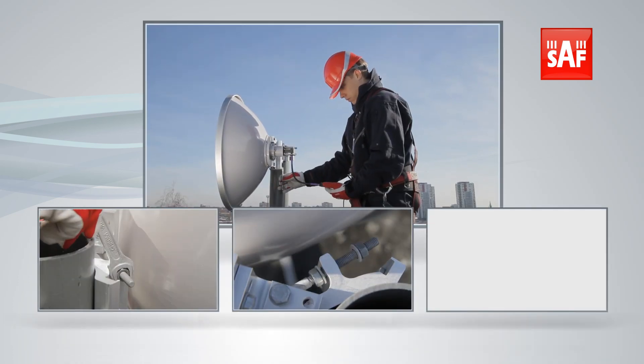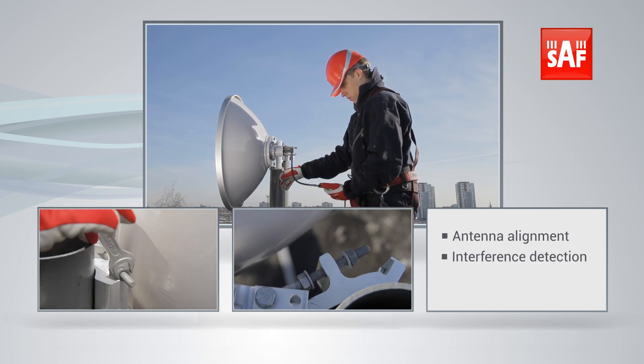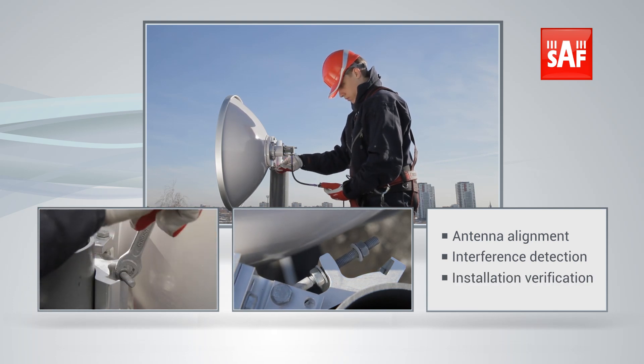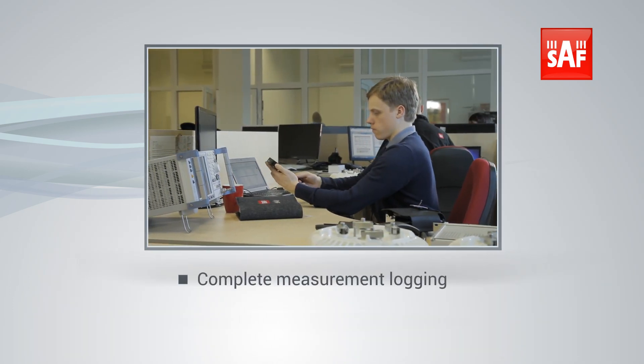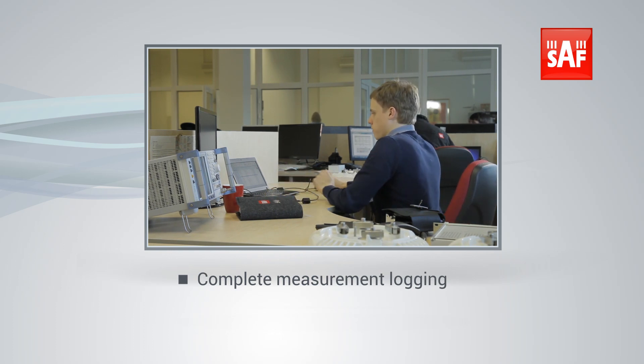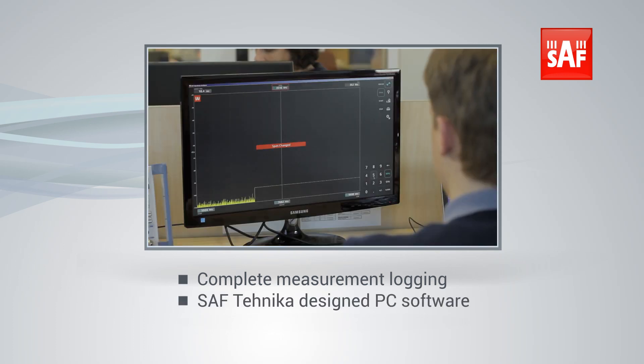With the Spectrum Compact, it's possible to make quick and precise antenna alignment, detect interference, or verify an already installed link. Data logging of all spectrum scans is available on the device, with enhanced data processing and analysis available via SAF Tehnika designed PC software on your laptop.